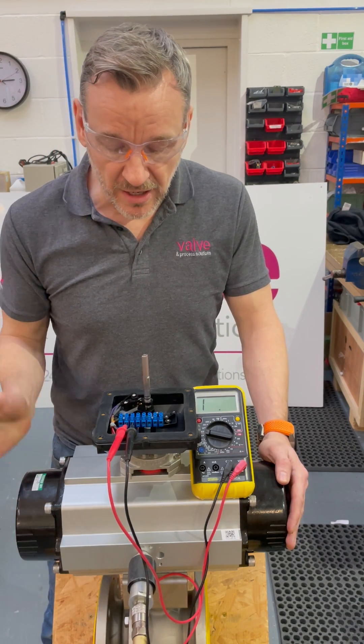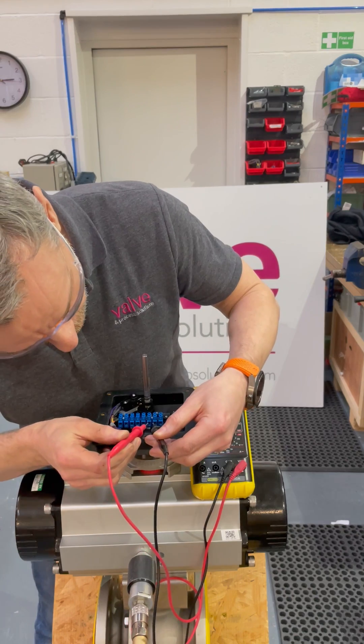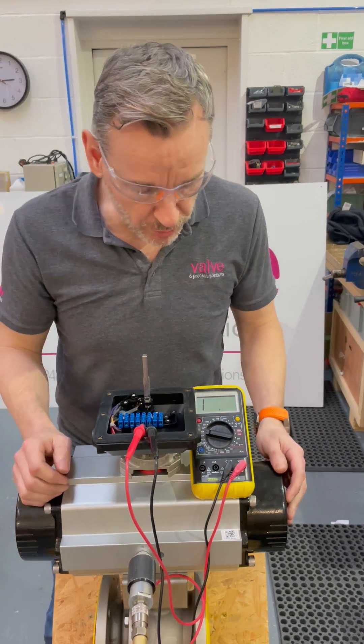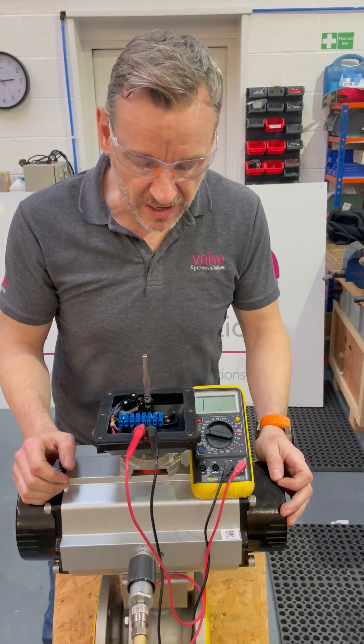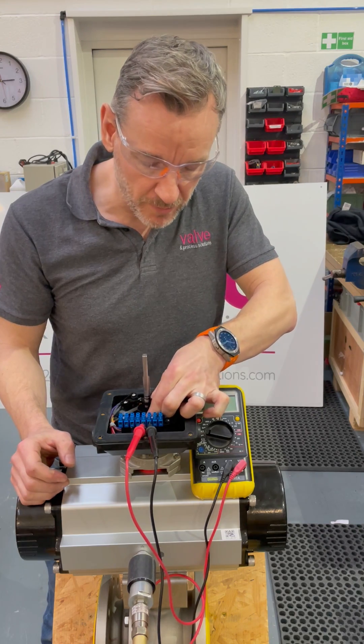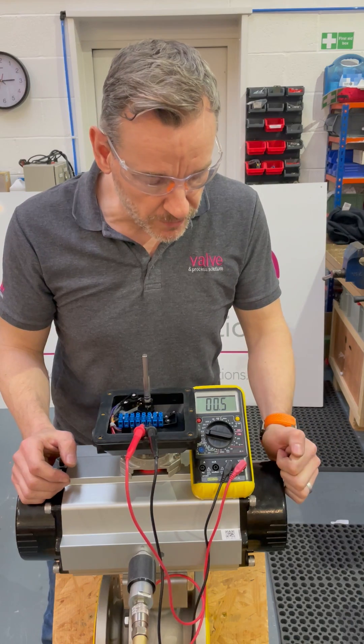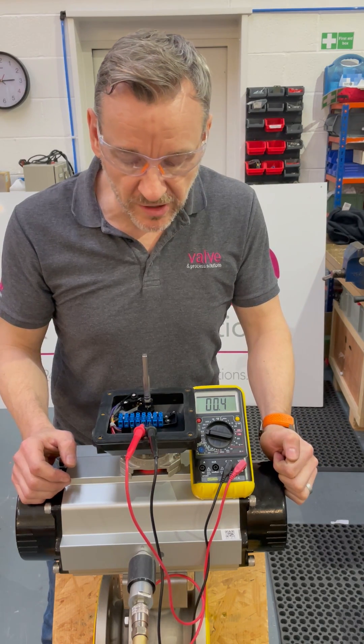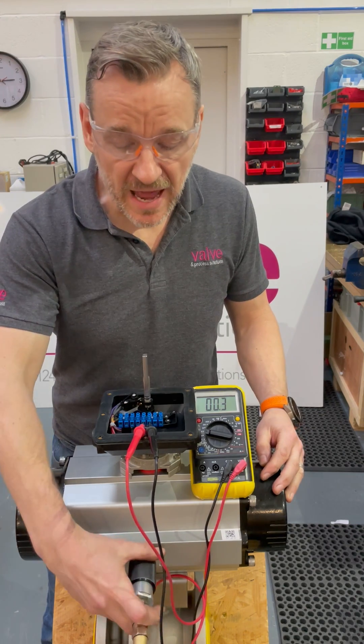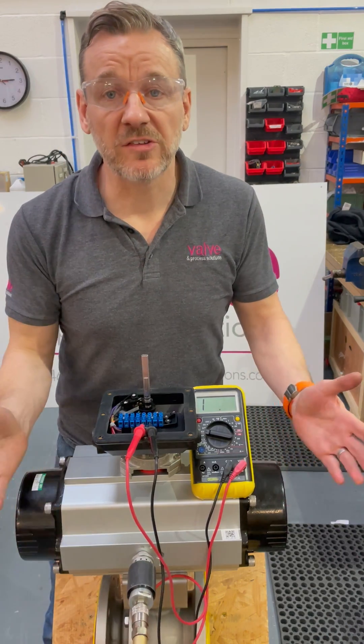Then I energize the valve, put some air into the actuator, the actuator moves to the fully open position, and then I move across onto my next two points on the terminal strip. You can see there's no continuity, so again I basically lift the bottom cam and turn it round until I get the audible sound and the tone disappears, and I know that switch is set.